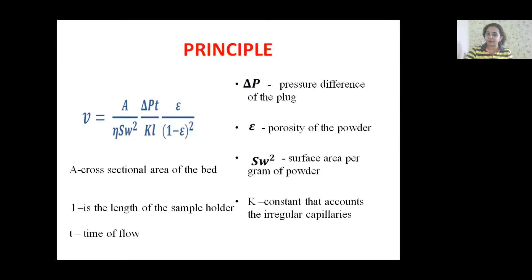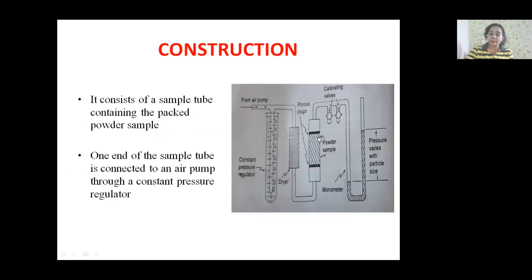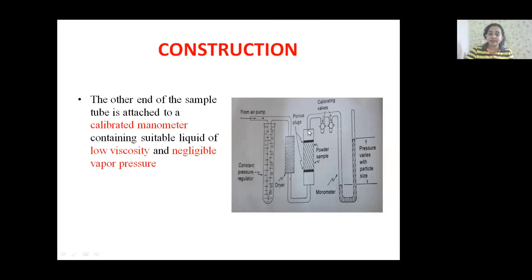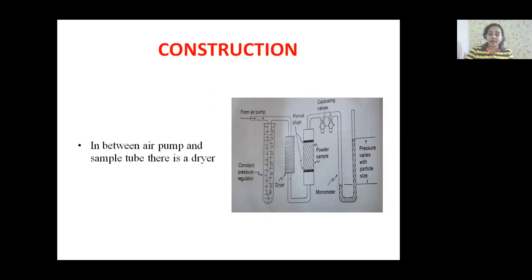Moving on to the construction of the Fischer Sub-Sieve Sizer instrument — it consists of a sample holder or sample tube in which the powder sample is packed. One end of the sample holder is connected to an air pump via a constant pressure regulator, and the other end is connected to a calibrated manometer containing a liquid of low viscosity and negligible vapor pressure. In between the air pump and sample holder, there is a dryer.